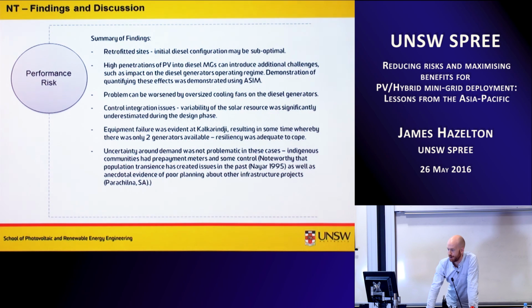As the project manager at Power and Water pointed out, you can actually worsen this problem because quite conservative utility generator designers will factor in a substantial safety factor when sizing the cooling fans for these generators, because it's really hot - Ti Tree's just north of Alice Springs, so up to 50-degree days. What they'll tend to do is design the system to operate at full load on the hottest day of the year. That's reasonable if you're talking about system reliability, but when the system was designed that way and then you integrate solar, you're exposing it to a lot more reduced-temperature operation, and that agitates these problems we have in terms of lower operating ranges.